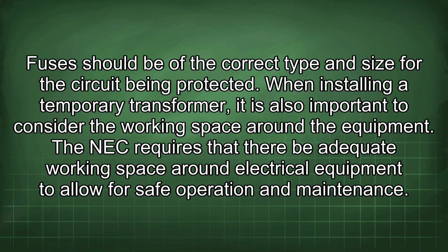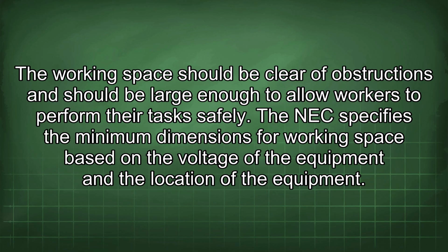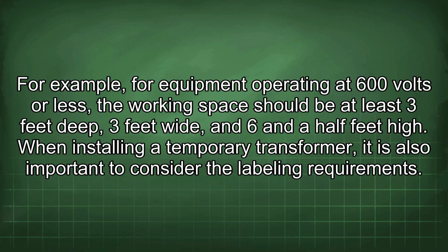When installing a temporary transformer, it is also important to consider the working space around the equipment. The NEC requires that there be adequate working space around electrical equipment to allow for safe operation and maintenance. The working space should be clear of obstructions and should be large enough to allow workers to perform their tasks safely. The NEC specifies the minimum dimensions for working space based on the voltage of the equipment and the location of the equipment. For example, for equipment operating at 600 volts or less, the working space should be at least 3 feet deep, 3 feet wide, and 6.5 feet high.